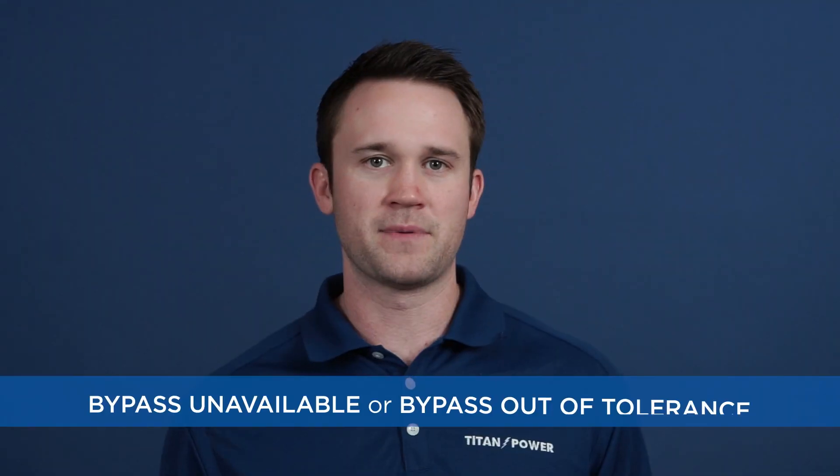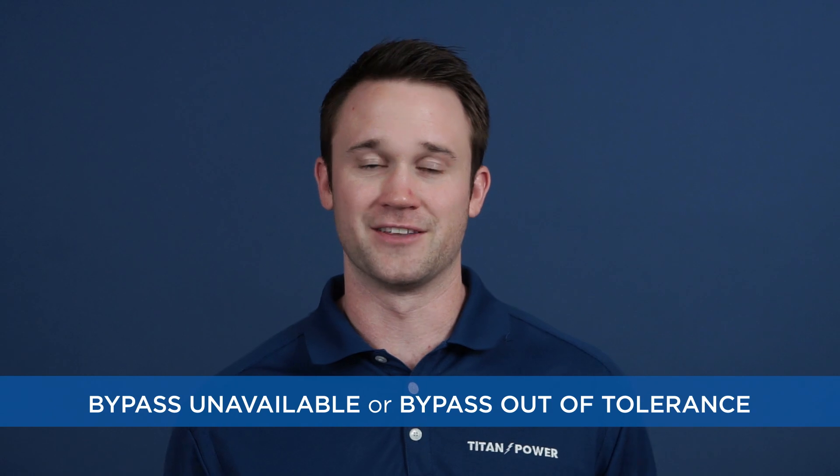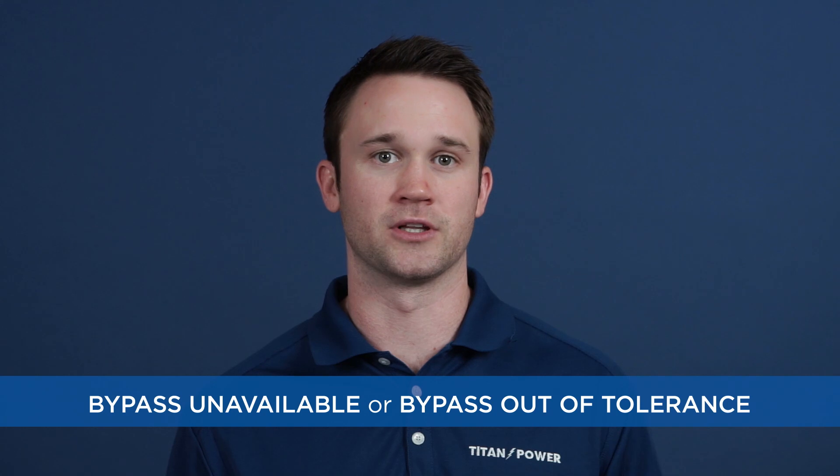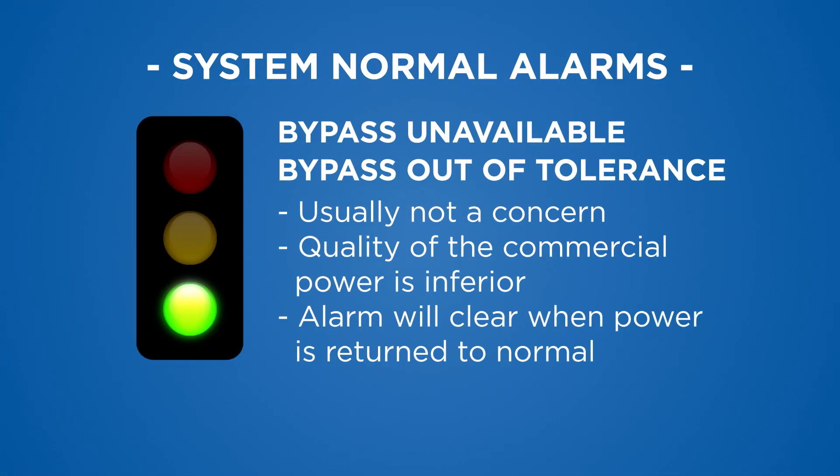Finally, there are system normal notifications. In many cases, a UPS notification is not an emergency at all and does not require a phone call or a dispatch — these are simply notifications to let you know that the UPS has done its job and the system is functioning as it should. Examples include bypass unavailable or bypass out of tolerance, which means there is likely a utility power issue. However, the UPS is still supporting the load. This is simply telling you that the quality of the commercial power seen by the UPS is inferior, and the alarm should clear on its own once utility power returns to normal.